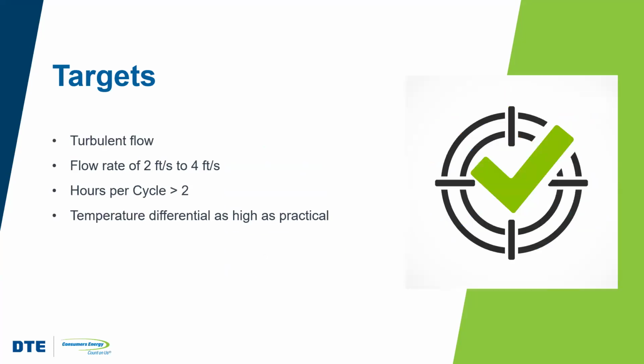All right, some targets that we have for that distribution system. We want to make sure that we've got turbulent flow, right? We want that turbulent flow so that we've got good temperature mixing. We don't want laminar flow. Like if we're looking at ductwork, we might want laminar flow because we want smooth duct flow. We want airflow.